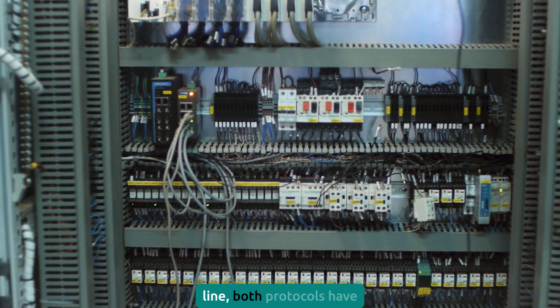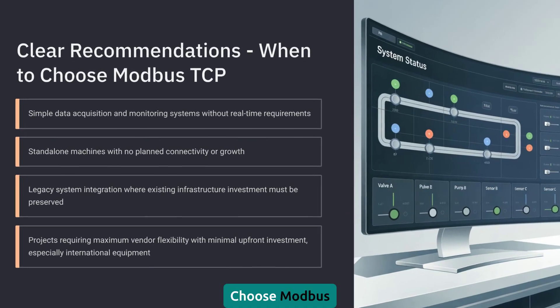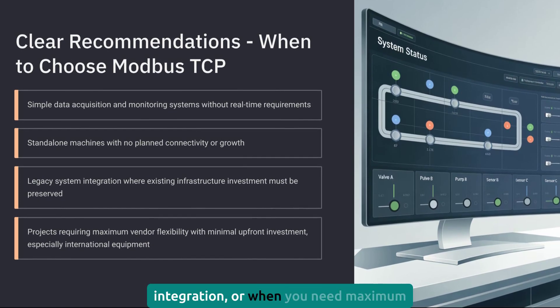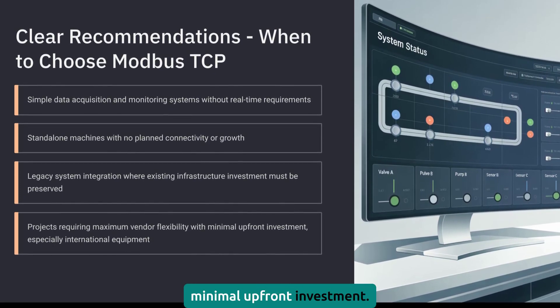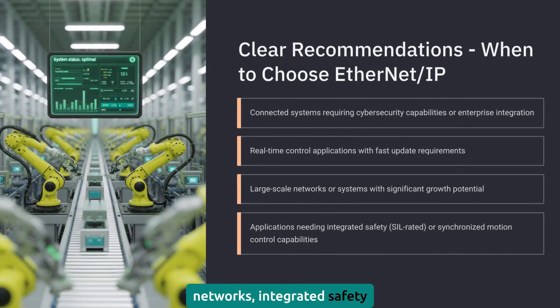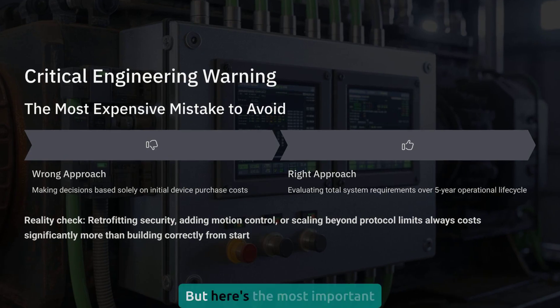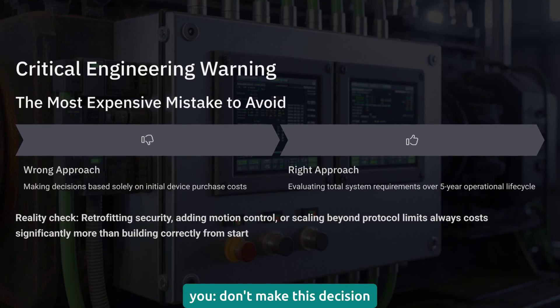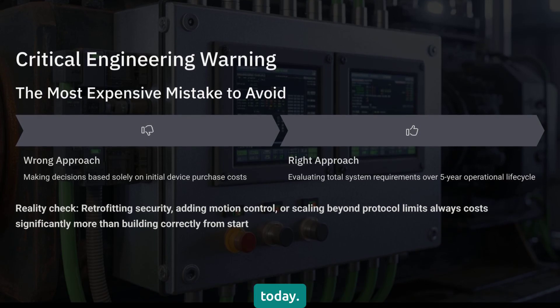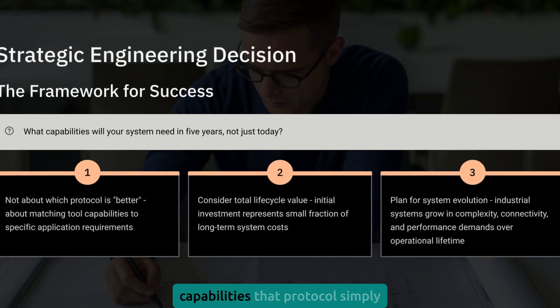Here's my bottom line: both protocols have earned their place in industrial automation, but they're tools for fundamentally different jobs. Choose Modbus TCP for simple data acquisition, standalone machines, legacy system integration, or when you need maximum vendor flexibility with minimal up-front investment. Choose EtherNet/IP for connected systems, real-time control, large-scale networks, integrated safety or motion, or any application where you might need native cybersecurity capabilities in the future. Most importantly: don't make this decision based solely on initial device costs. Think about where your system needs to be in 10 years, not just where it is today. The biggest mistakes happen when someone chooses the cheaper option up front, then discovers they need capabilities that protocol simply cannot provide.